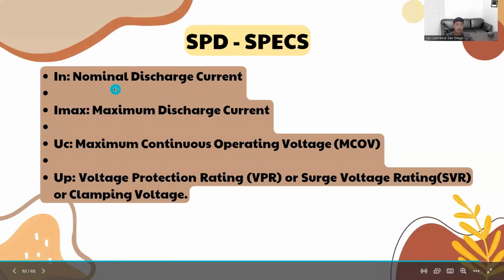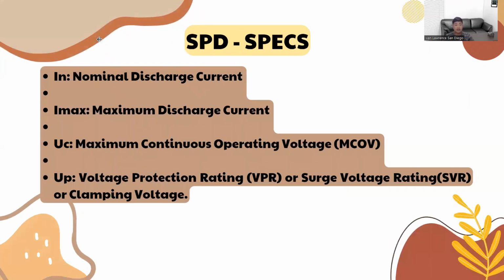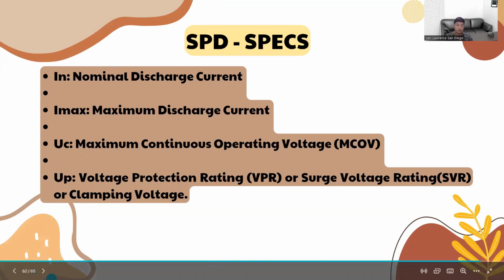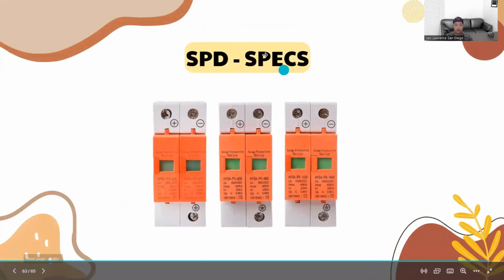SPD specs. In, nominal discharge current, IMAX, maximum discharge current. UC, maximum continuous operating voltage or MCOV. UP, voltage protection rating or VPR, or surge voltage rating SVR or clamping voltage. These are the SPD specs.